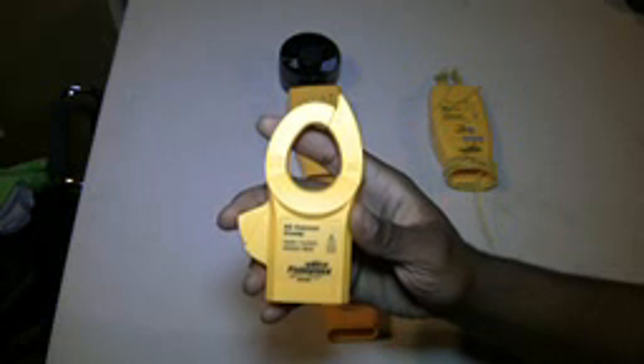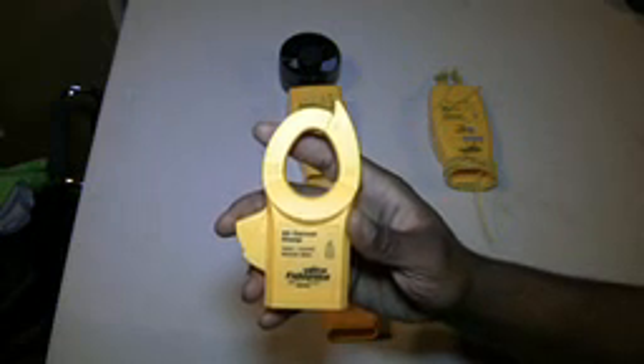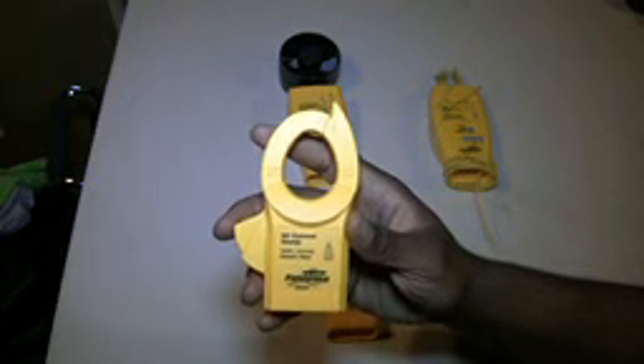I forgot where I left off, so basically I'm just going to go into details about each specific piece here. With the ACH4, hopefully you can see that pretty good, the main reason why I got this is to be able to check the amperage on the blower motor inside the unit with the blower door closed. As you well know, the majority of us check the amperage on the blower motor with the blower door open, understandably, because we don't have anything to attach it to and let the blower door be closed.